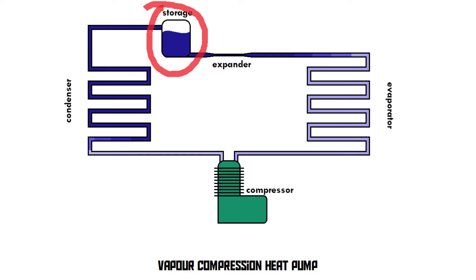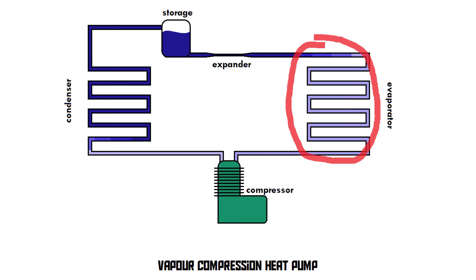Let's walk through the entire system starting inside the storage tank. The refrigerant there is in liquid form at around room temperature, about 20°C. The liquid refrigerant first goes through the expander and then enters the evaporator. Inside the evaporator, the pressure is very low, which means the boiling point of the refrigerant is much lower than before, so the relatively warm liquid refrigerant immediately boils and starts to evaporate.